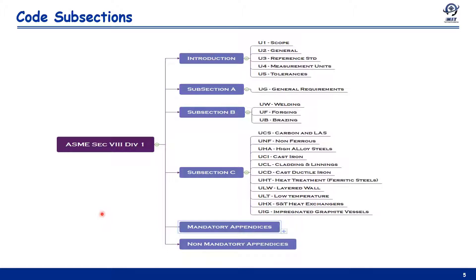The code subsections begin with an introduction containing the U section from U-1 to U-5. The code is further subdivided into three subsections: A, B, and C. Subsection A contains general requirements (UG) common for all pressure vessels. Subsection B contains requirements related to method of fabrication — UW for welding, UF for forging, and UB for brazing.